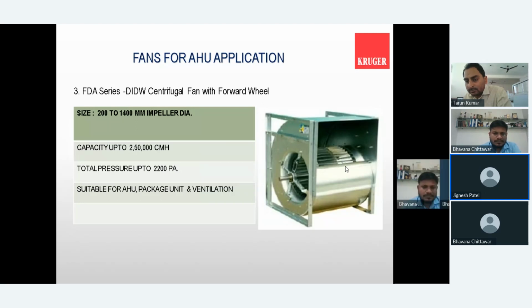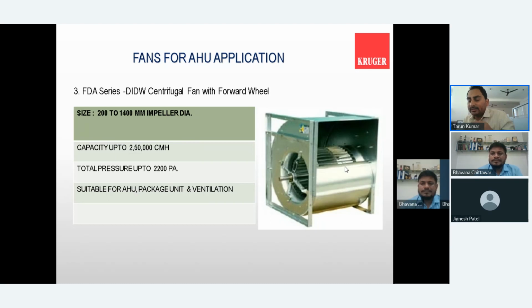So you mean to say that if I rotate a backward direction fan in the forward direction, what will it do? Will it do reverse suction? Reverse suction, yes sir. That's why, when going for approval, we always confirm with the client whether it is counterclockwise or clockwise. Protection also has to be taken care of so that it does not rotate in the reverse direction. Yes sir. So whenever we take the GAD approval, we always confirm with the system, with the contractor, what exactly direction is required, like if their duct rotation is on some other side, we have to go with counterclockwise. That depends completely on the duct routing.